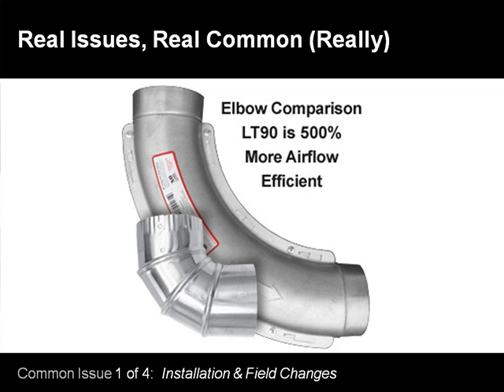For example, you measure resistance of duct by equivalent feet. So how long is the duct? An elbow would be an equivalent length of straight duct. So a rectangular elbow would be around 65 feet of duct. I just pulled a few examples off the SMACNA charts. And if you put turning vanes in there, it goes down to 14 feet of duct. So you can imagine on a large duct system, these wrong selected fittings create horrendous problems down the line.